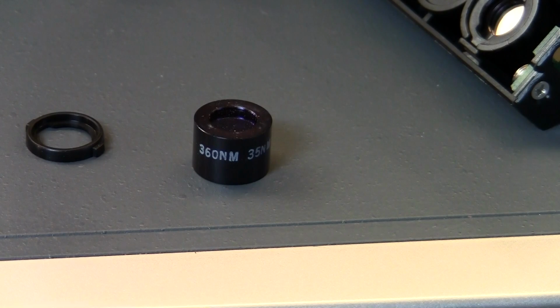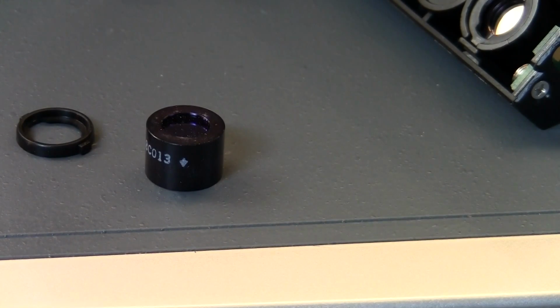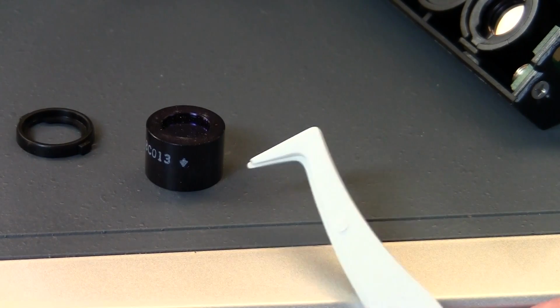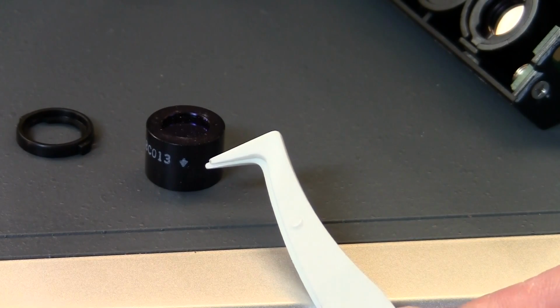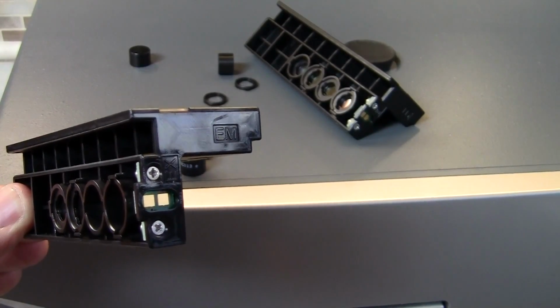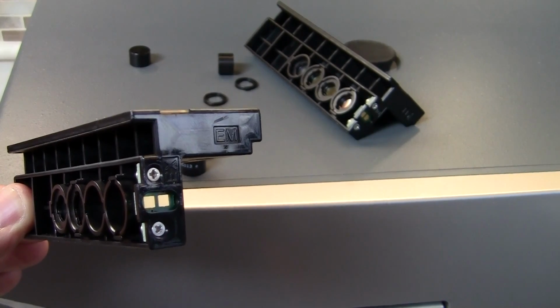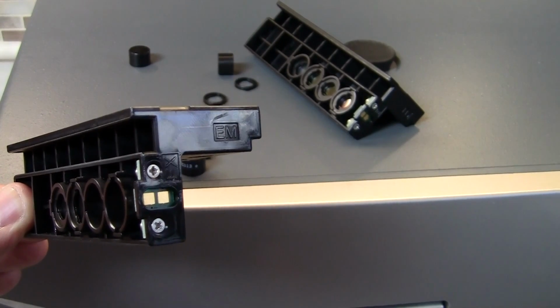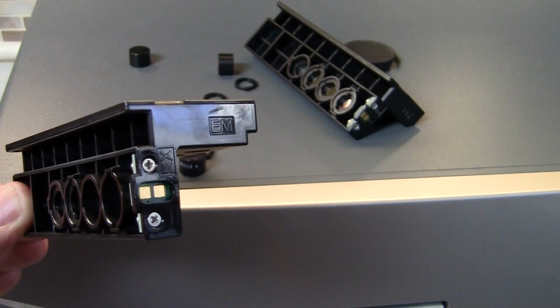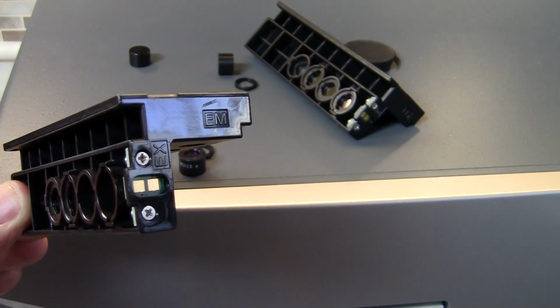When placing filters in the holders, you have to be mindful that there is a direction through which the light should pass through the filter. Typically, light will pass from the top through the bottom of the filter. Many filters actually have an arrow on the side indicating the direction through which the light should pass. Because light is passing through the filter holder in a particular direction, you have to orient the filters to make sure that the filter arrows are pointing in the direction the light is traveling.